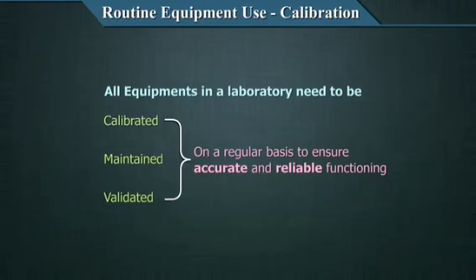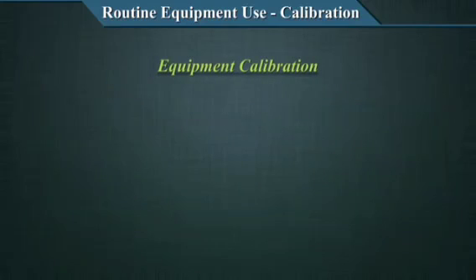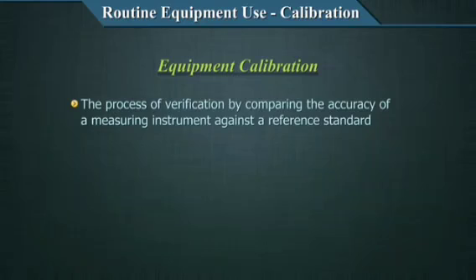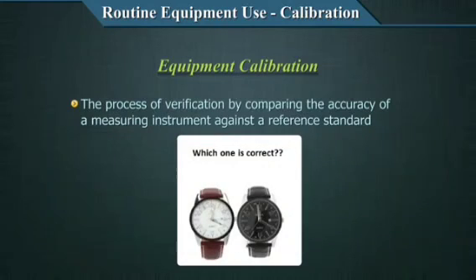Let's examine the details of calibration. Equipment calibration can be defined as a process of verification by comparing the accuracy of a measuring or a test instrument against a reference standard. Would like to mention here that calibrations are required both for equipment and for your analytes that you are using in the equipment. So how does that work?